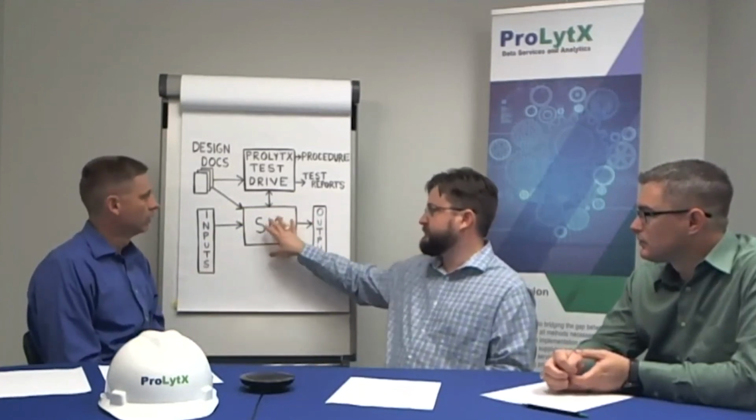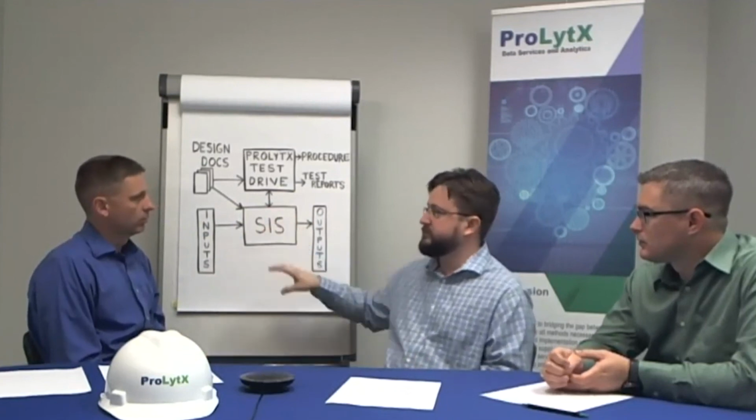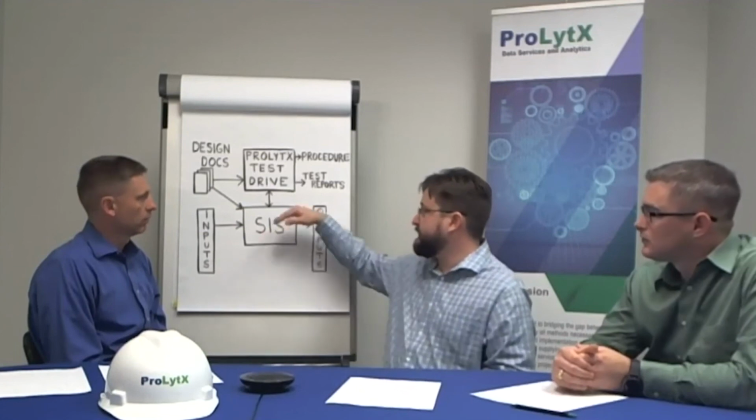And because we're doing this with a computer and it's in simulation, we have those kinds of capabilities. Whereas with a standard procedure, you might only be checking the 3 or 4 things you're expecting to occur. We can actually check the entire list of outputs for a facility. We can get everything up and running and healthy, trip a portion of it, and check to make sure it did not cause a trip of a portion of the facility that was not supposed to trip.